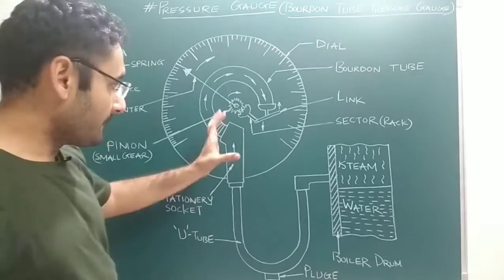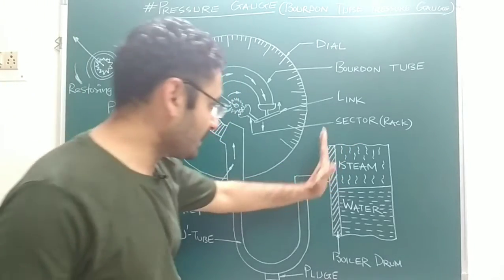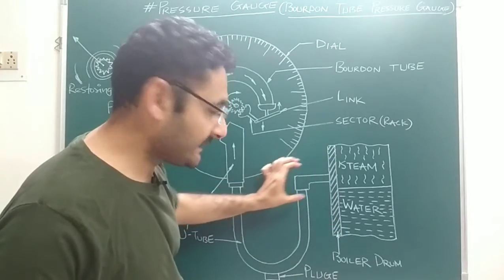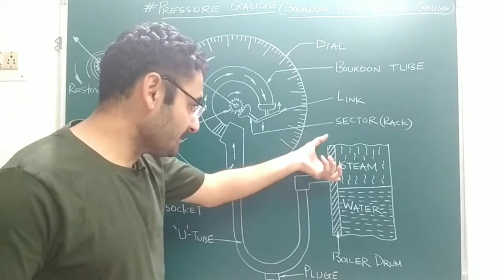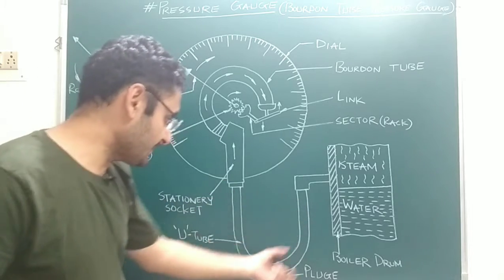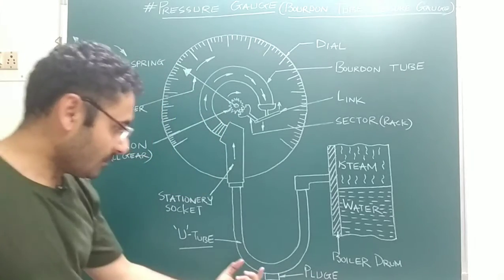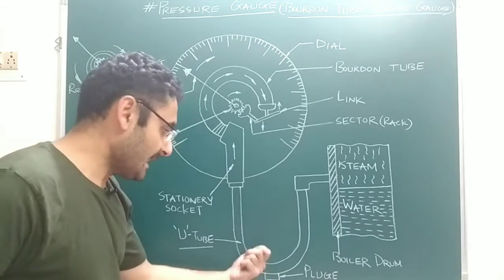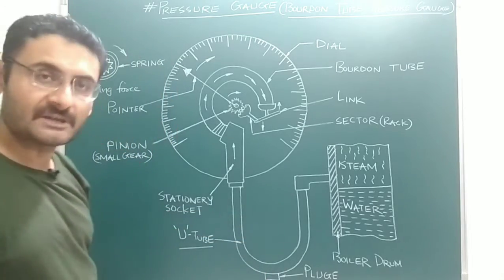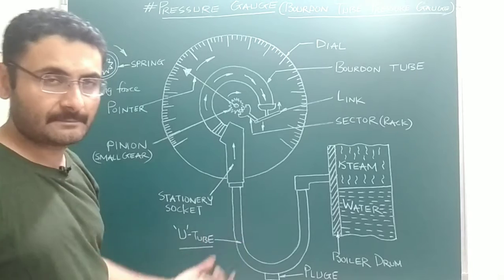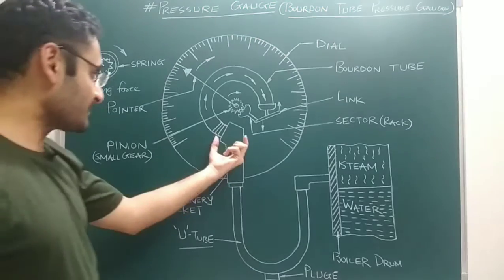Now for construction: the pressure gauge is connected with the steam portion of the boiler drum. The steam portion of the boiler is connected with a U-tube. The U-tube is connected with one plug. The use of that plug is that when you open it, any dust, dirt, and scaling inside the pressure gauge can be removed — so the plug is used for cleaning purposes.